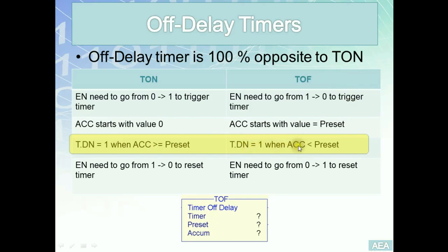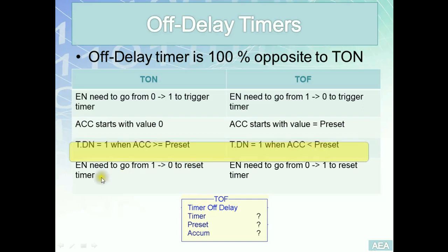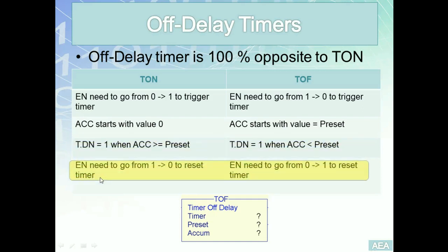Opposite to this fact for the TOF, the done bit will be set to one as long as the accumulator is strictly less than the preset value. The final point: enable bit has to go from one to zero to reset the timer. In other words, we need to have logic discontinuity across the rung that includes the timer and the TOF to reset it.